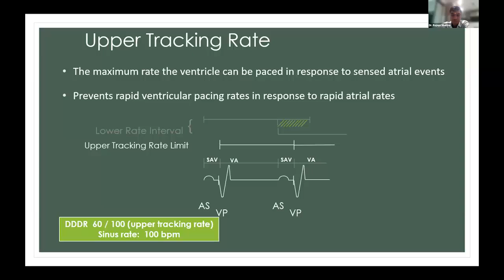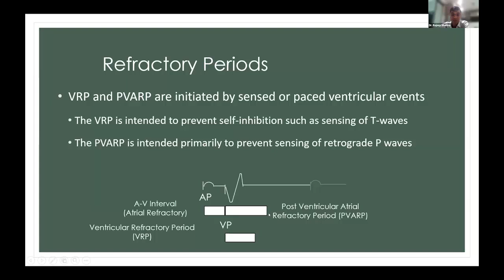Refractory periods: there is the ventricular refractory period and the post-ventricular atrial refractory period, initiated by sensed or paced ventricular events. VRP is intended to prevent self-inhibition, such as sensing of T waves, because once ventricular pacing starts, there will be T waves which can be sensed, and there will be pacing inhibition. And PVARP, the post-ventricular atrial refractory period, is intended to prevent sensing of the retrograde P wave. I'll discuss this. So this is an atrial pace event. After that, the AV delay will be there, then a ventricular pace event. After that, the ventricular refractory period is there, and the post-ventricular atrial refractory period is there. This is more useful in clinical scenarios.